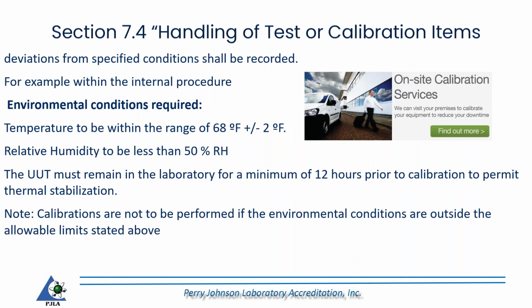Most of the time, I feel that this is in regards to environmental conditions. And this is one thing: have the on-site calibration services. When you're going on site and doing testing or calibration, the environment may not be as friendly as it is in the confines of the fixed facility. So deviations from specified conditions shall be recorded.